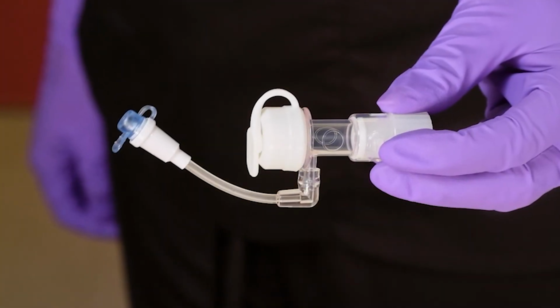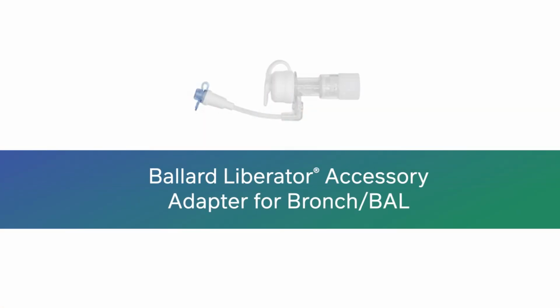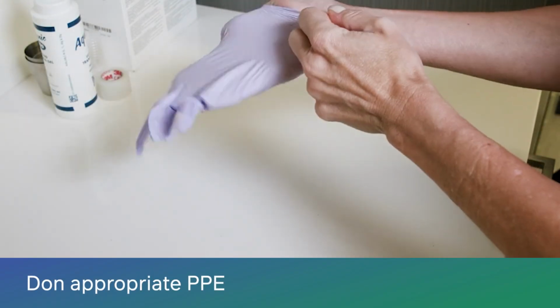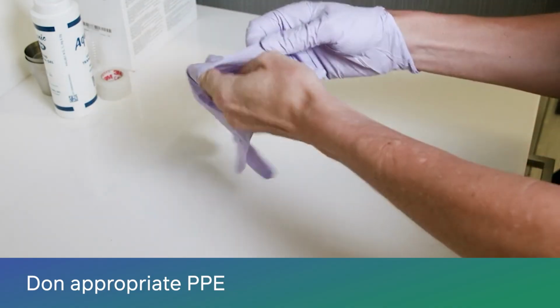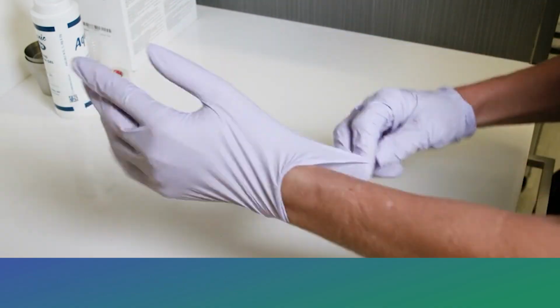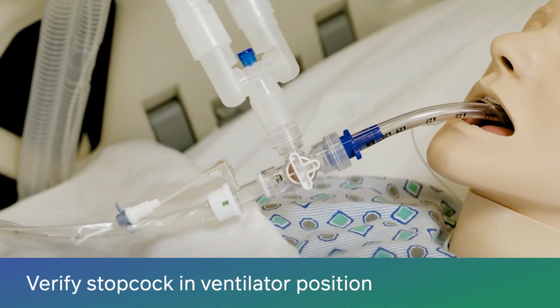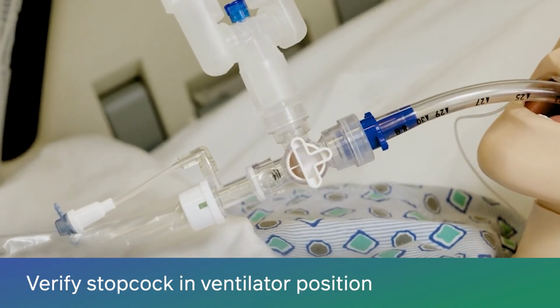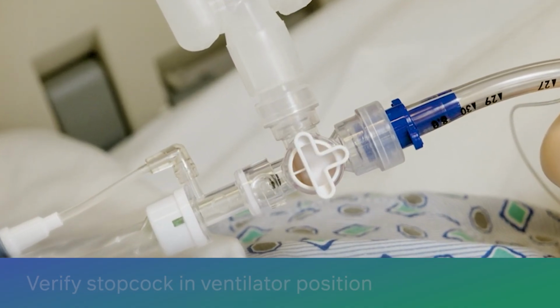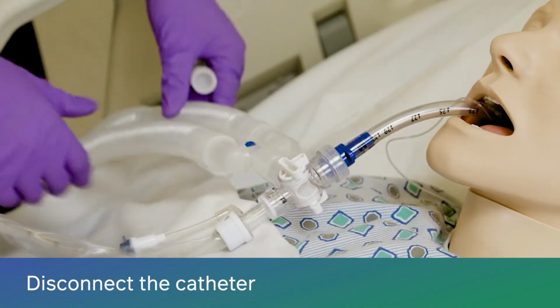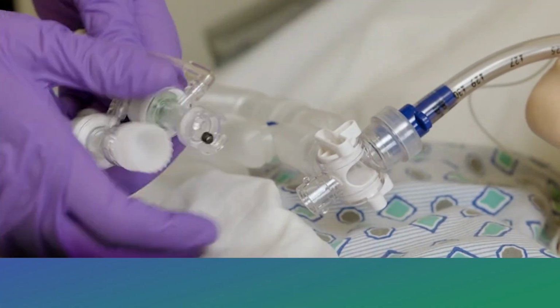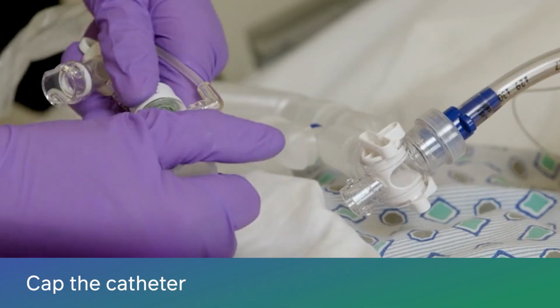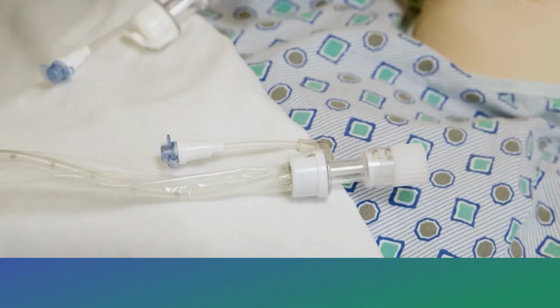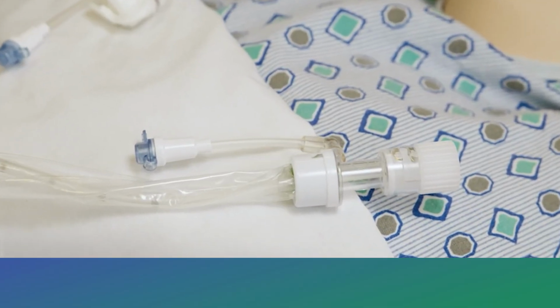When using this system for procedures such as bronchoscopy or mini BAL, utilize the Ballard Liberator accessory adapter for BronchBal. Before beginning the procedure, wash your hands and don appropriate protective equipment, per your hospital protocol. Make sure that the stopcock on the manifold is turned off to the suction catheter and in the ventilator-only position. Carefully disconnect the catheter from the manifold by rotating counterclockwise. Remove the cap from the adapter and place on the closed suction system. Set the closed suction system aside.